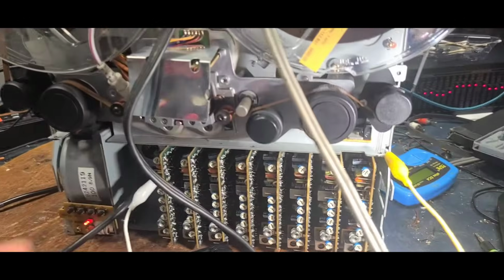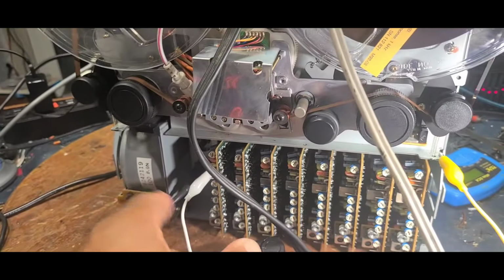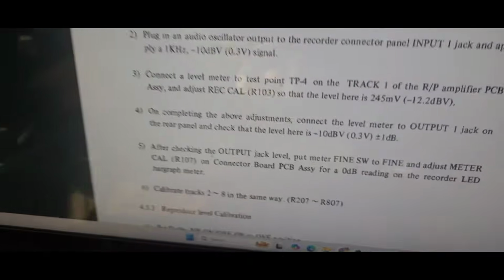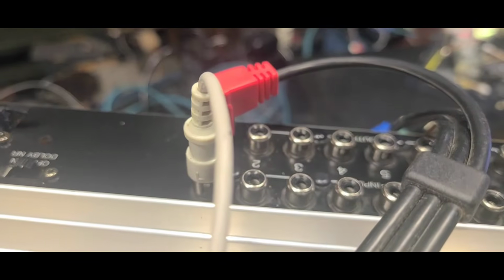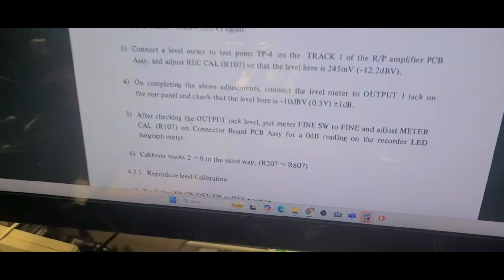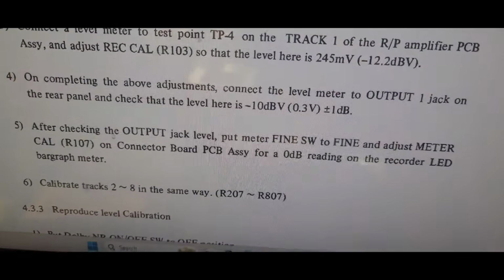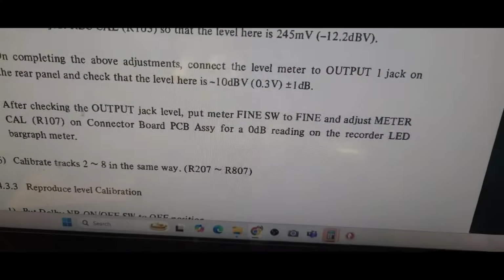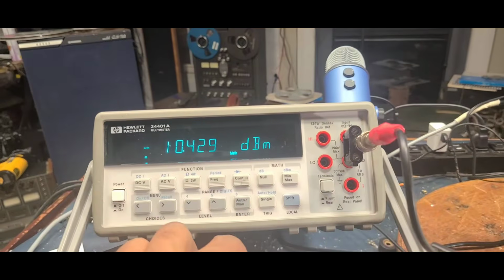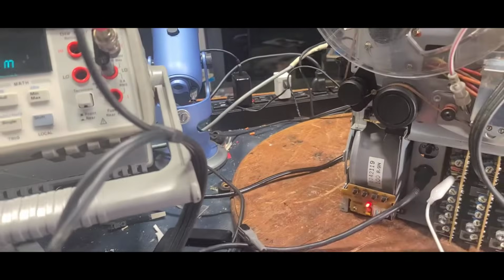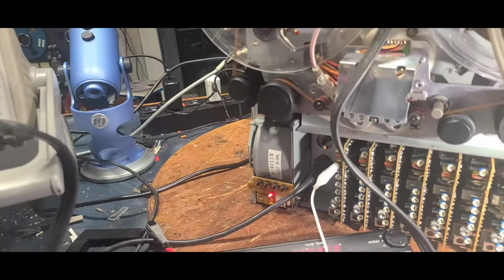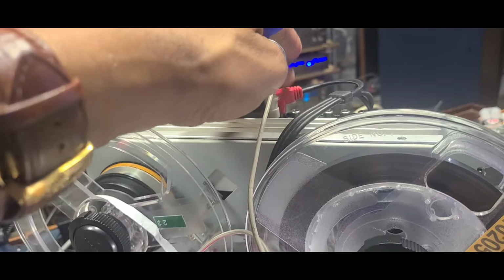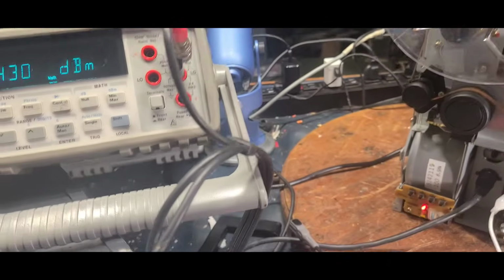multimeter. But that's kind of cumbersome to do for all the channels, because after we do that calibration and adjustment, it tells us to go back and measure the output of the unit, which is where that red RCA cable is, to make sure that we have a negative 10 dB signal at the output. And you see right now we're at negative 10.4. So instead of doing that middle calibration, I'm just going to skip over that and go directly to that check that we look for negative 10 dB at the output.